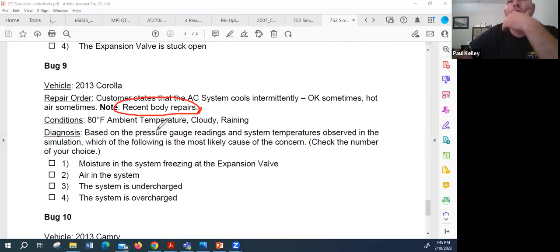But also just noting that it was fine—when it was working, it was working. So it's not undercharged, it's not overcharged, because that doesn't give us an intermittent. Now, I mentioned air in the system to you, but who remembers what air in the system causes? It increases the pressure, just sporadically, not all of a sudden make it low for a few minutes. So I would say no.